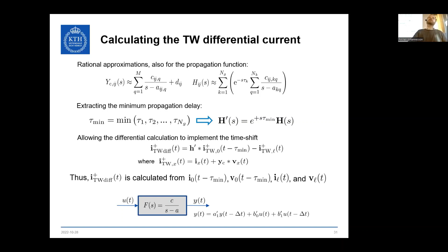Then you can actually remove this one, saying that the traveling wave differential current is calculated from the sending end sometime earlier, basically. So the sending end is always happening before the receiving end. And this helps out in the implementation, because that means that you can subtract this from your telecommunication delay. So even if you have a 2 millisecond time delay between sending and receiving end, the protection is not going to be that slow, because you can subtract this one.